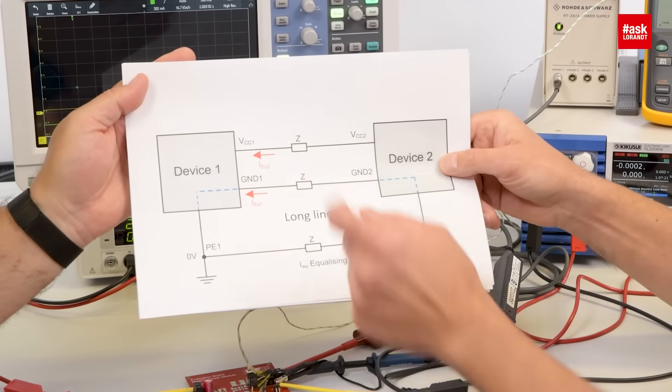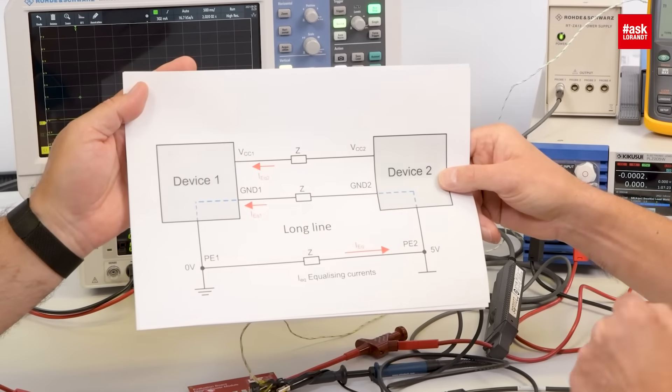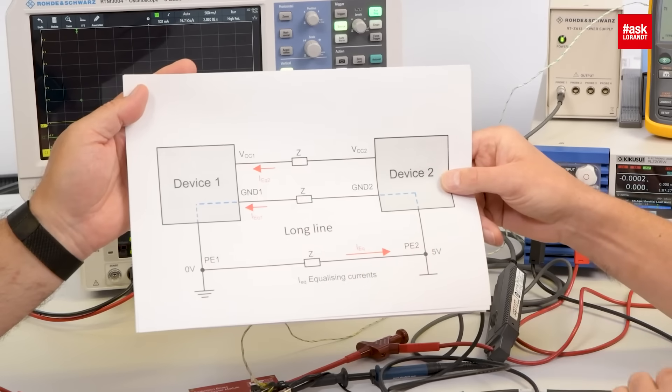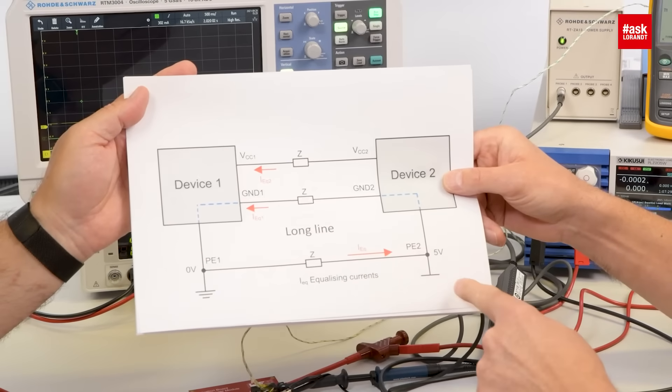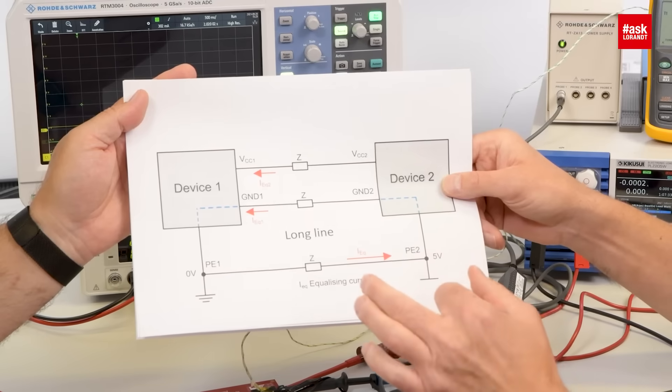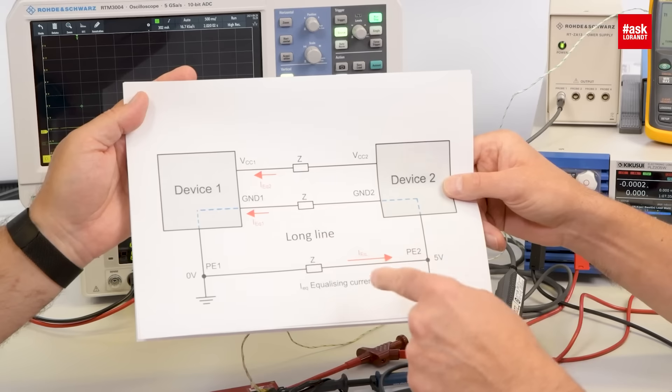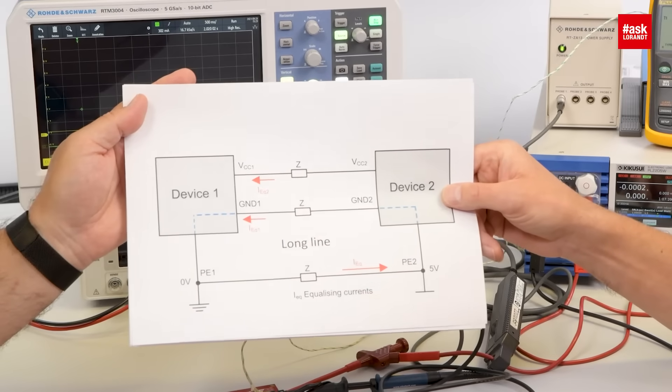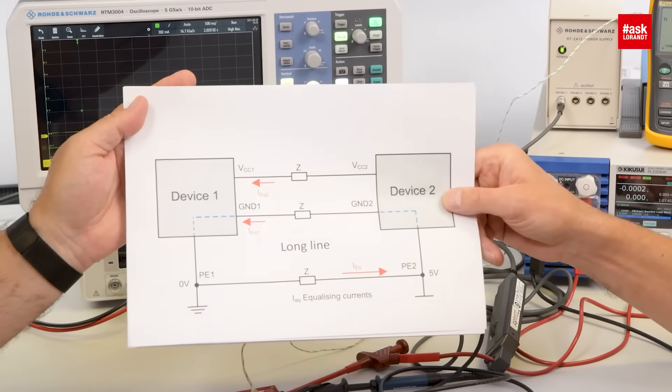If you have got device 1 and device 2 and all the ground potentials are here separated by a long cable, you will have an impedance there. And if you have got different potentials and an impedance, a resulting equalizing current will flow. This is why your data communication is disturbed.